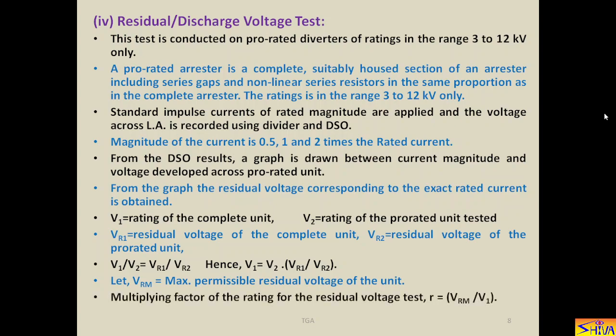Then the multiplying factor of the rating for the residual voltage test, R, will be equal to VRM divided by V1. VRM is the maximum permissible residual voltage of the unit and V1 is the rating of the complete unit. The diverter, that is the lightning arrestor, is said to have passed when VR2 is less than R into V2. Then we say that the lightning arrestor is sustaining the discharge current test as well as the discharge voltage test.